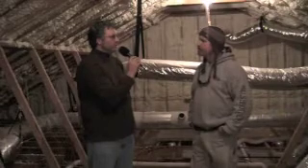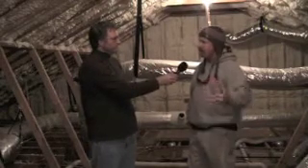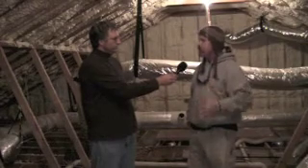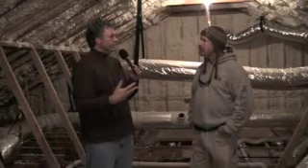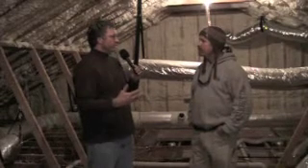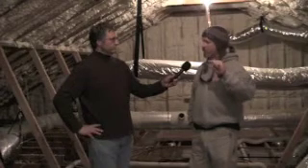What is a two-stage unit? What does that mean? The compressor has two stages of capacity, either 100% or 67%, and we call it first and second stage. So if it only requires it to run on the second stage, then it's using less energy, about 2/3 of its capacity to run and to be able to condition the home. And in a home like this, unless the differential, meaning what you're asking for on the stat versus what it is, is within the 3 or 4 degree range, 90% of the time we're running on the second stage.